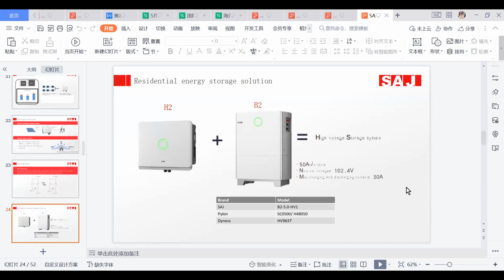And here are our B2 high voltage batteries. The capacity is 50 ampere-hour, and the nominal voltage is 102.4 volts, and the maximum charging and discharging current is 30 ampere. And we could also use these batteries from Pylon-Tech and Dyness.